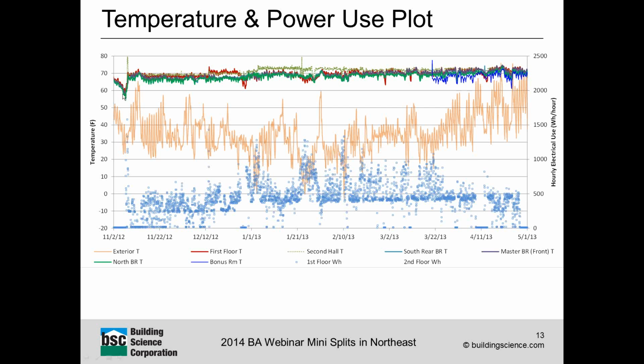They realized it was time to turn on the heating system, so you can see them slam it into gear, running for many hours at pretty high load. The maximum load for these systems is about 2,000 watts. It chugs along with very few hours at zero, modulating up and down based on outdoor temperature. At various points when it gets noticeably colder, there's a fair amount more electrical draw from the mini-split heat pump.